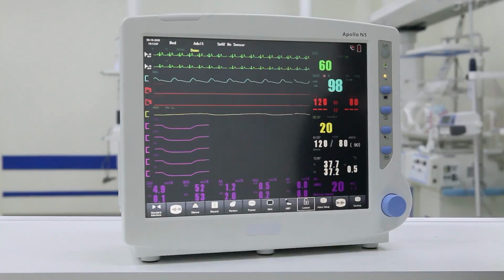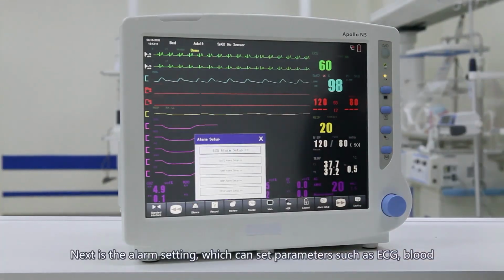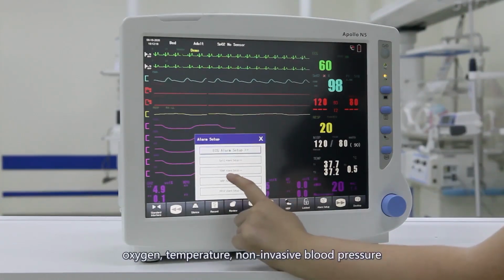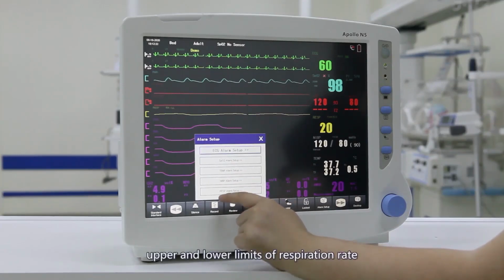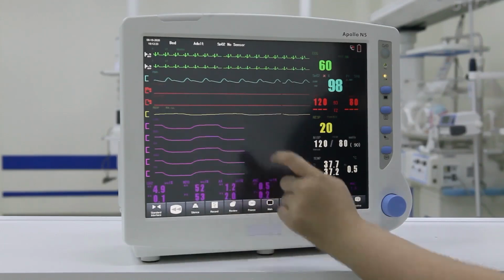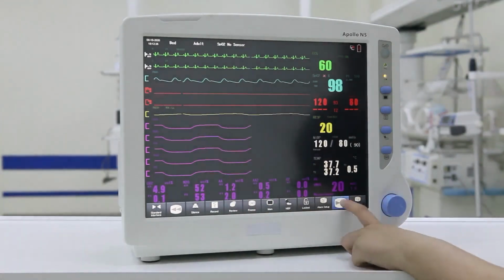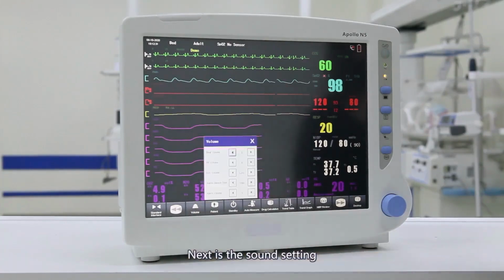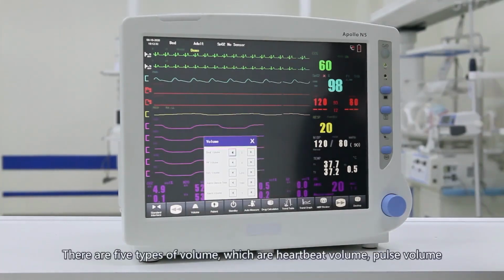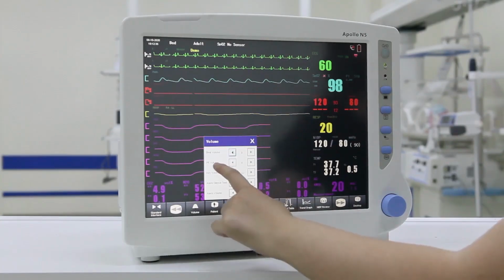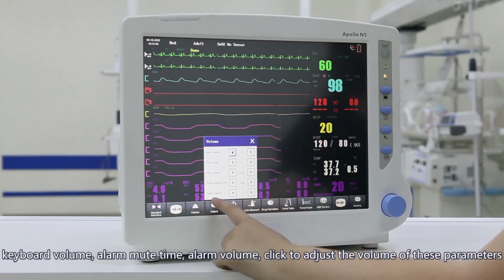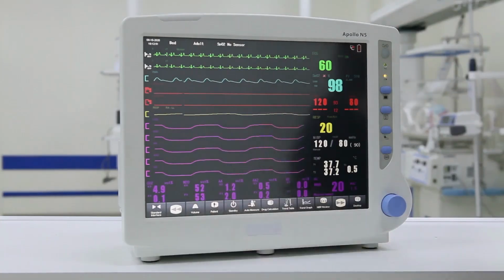Next is the alarm setting, which can set parameters such as ECG, blood oxygen, temperature, non-invasive blood pressure, upper and lower limits of respiration rate. Next is the sound setting. There are 5 types of volume, which are the heartbeat volume, pulse volume, keyboard volume, alarm mute time, alarm volume. Click to adjust the volume of these parameters.